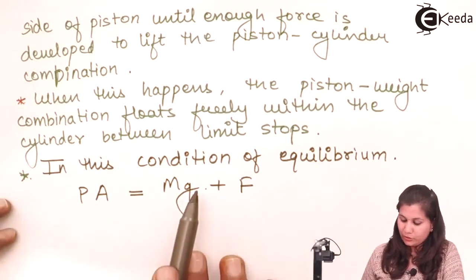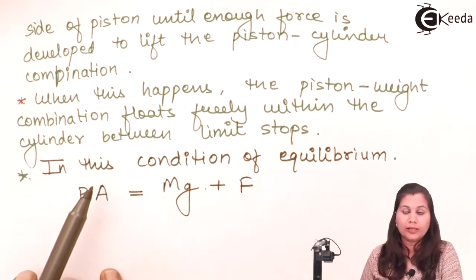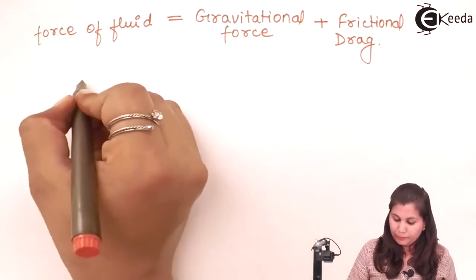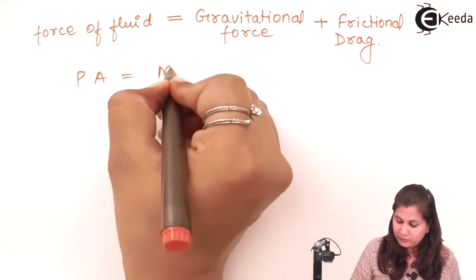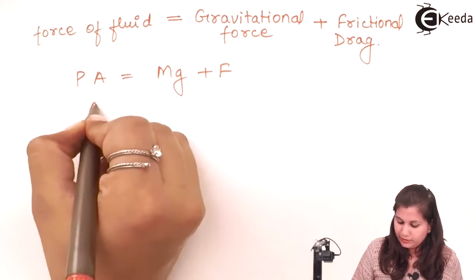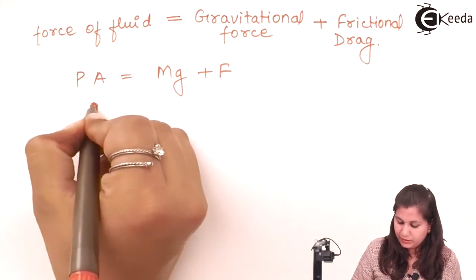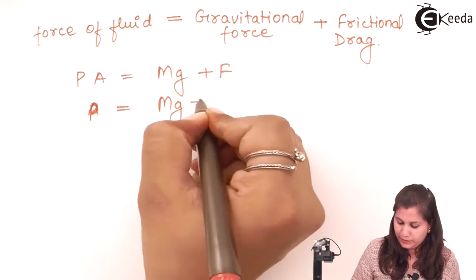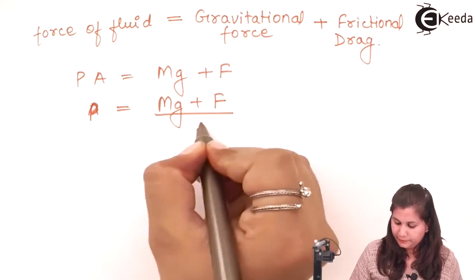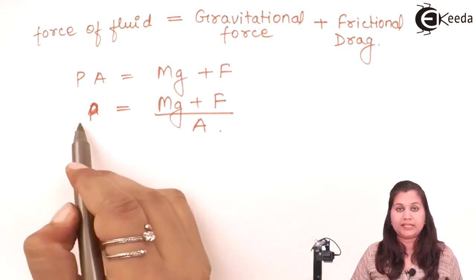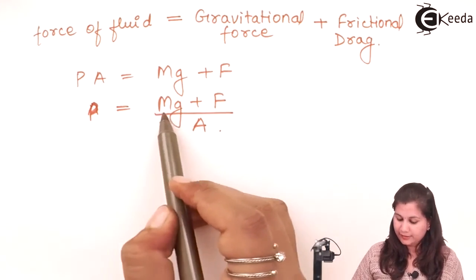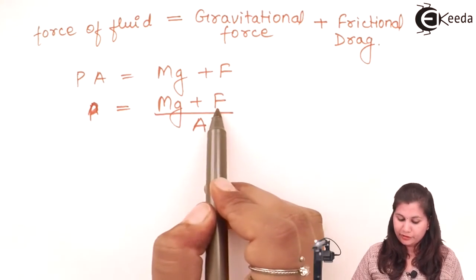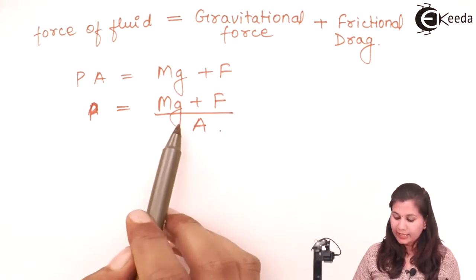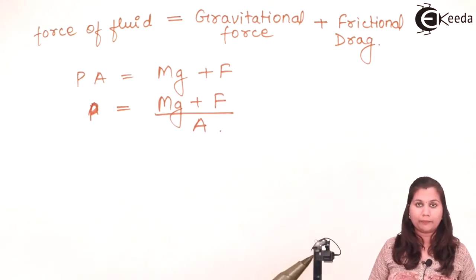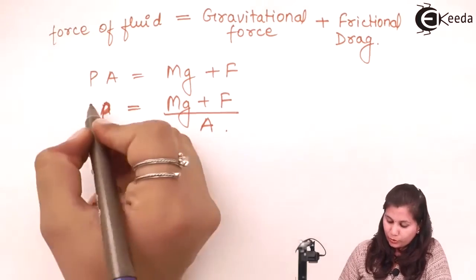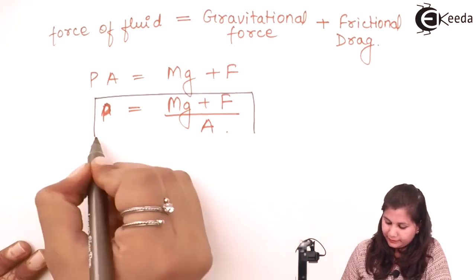Now from this equation, if we find out the value of the pressure, that is P. So PA is equal to mg plus F. So the pressure P is equal to mg plus F divided by A. Where P is the pressure, m is the mass, g is the acceleration due to gravity, F is the frictional drag, and A is the equivalent area of the piston cylinder combination. So pressure is equal to mg plus F divided by A.